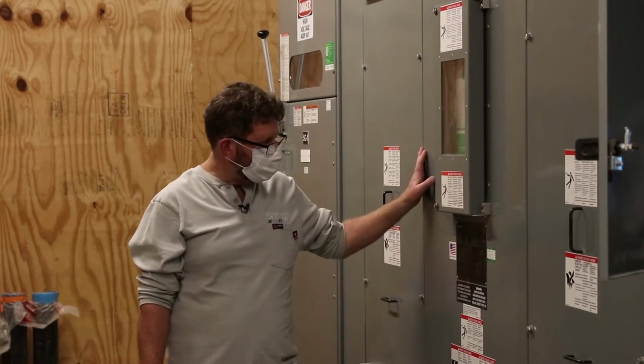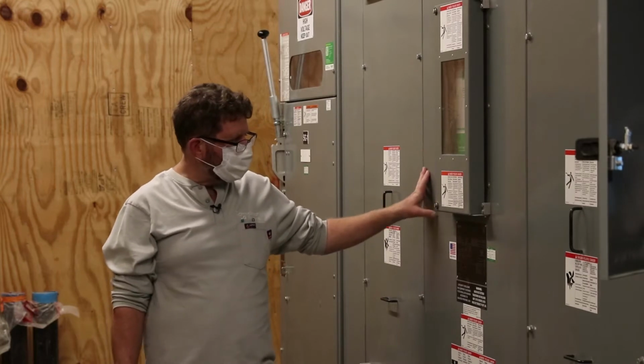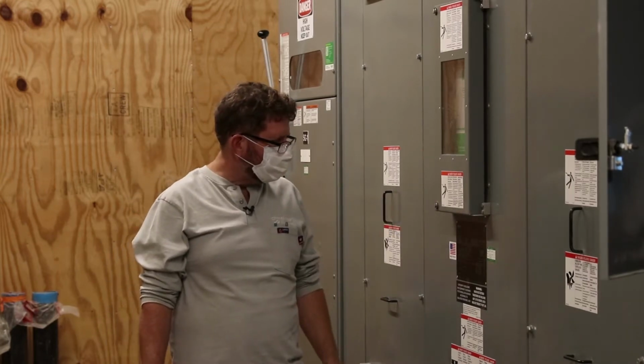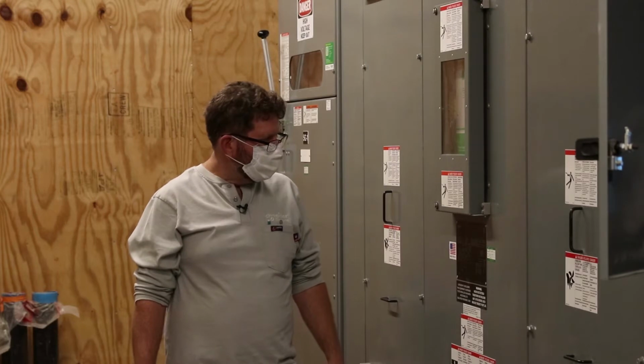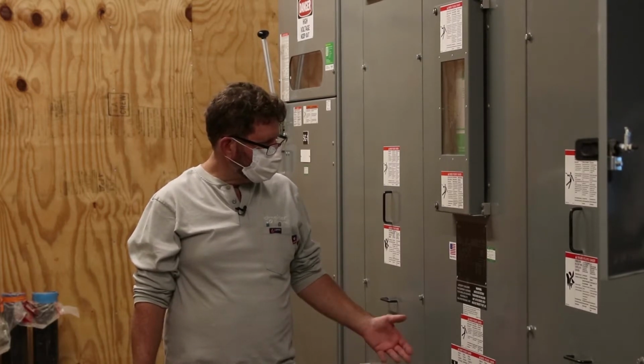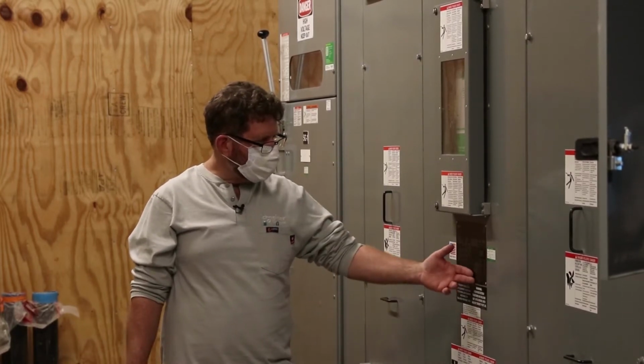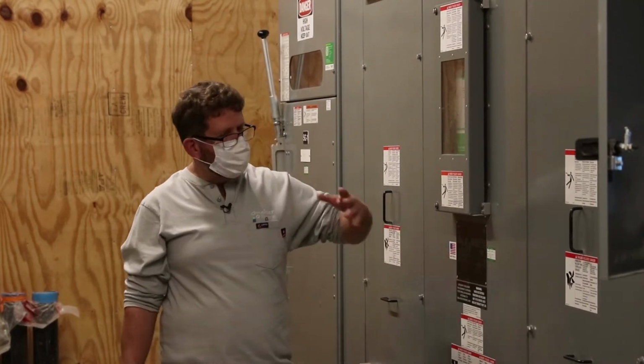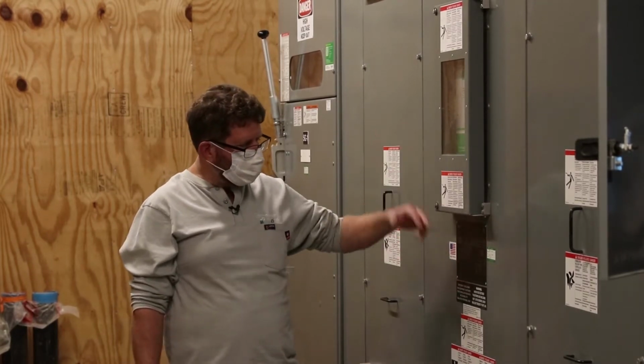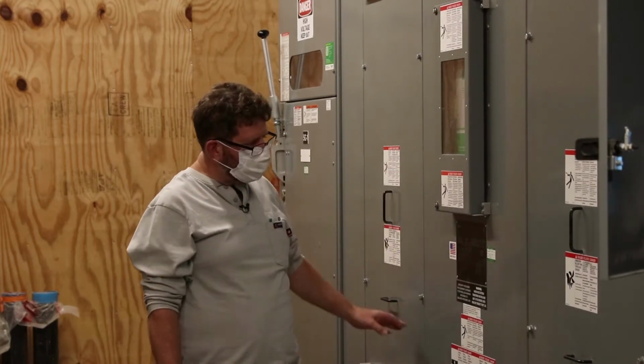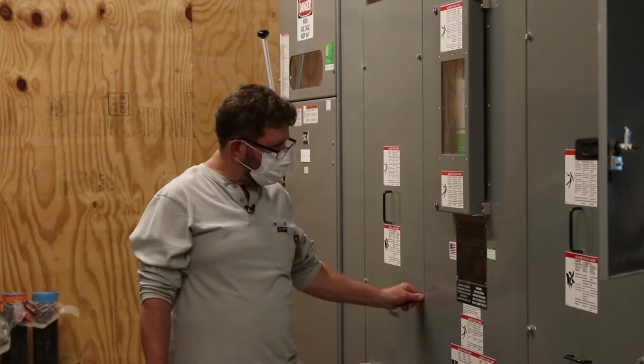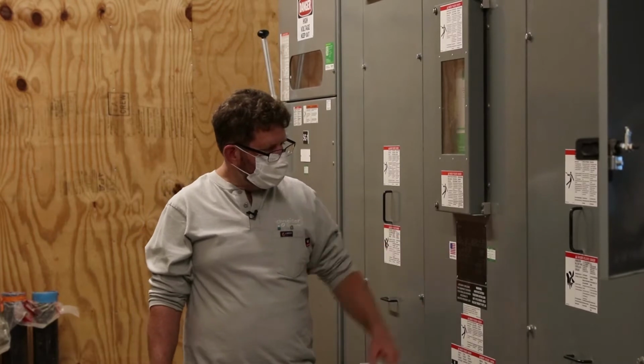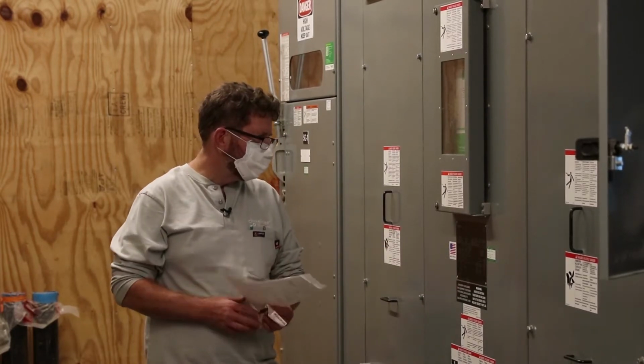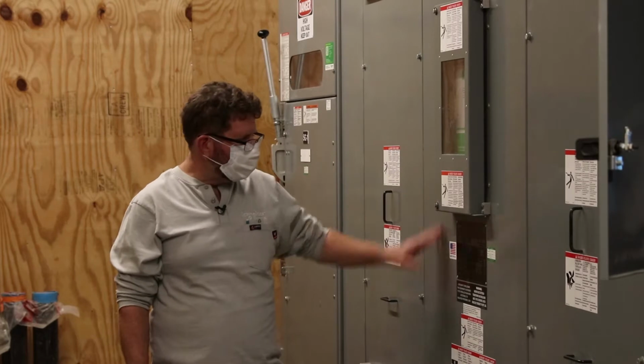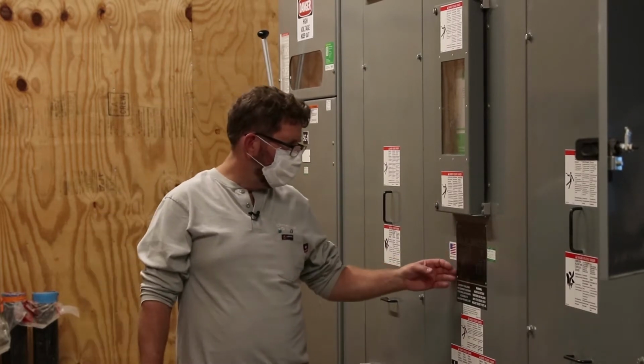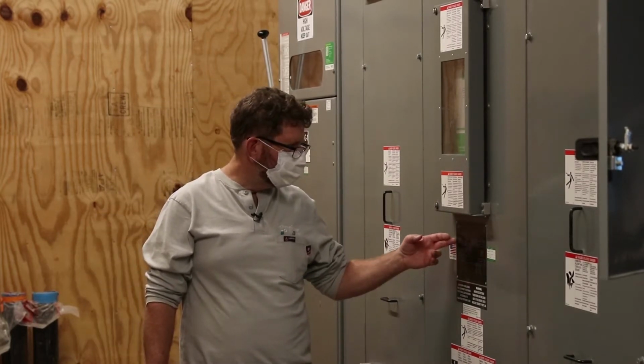So a 2000 kVA transformer takes 4,160 volts and transforms it down to 480/277. You have multiple taps on the transformer. If you find that your voltage isn't what you need it to be, high or low, you can shut down the switchgear and change the taps to accommodate that. These transformers are all made in Bland, Virginia.